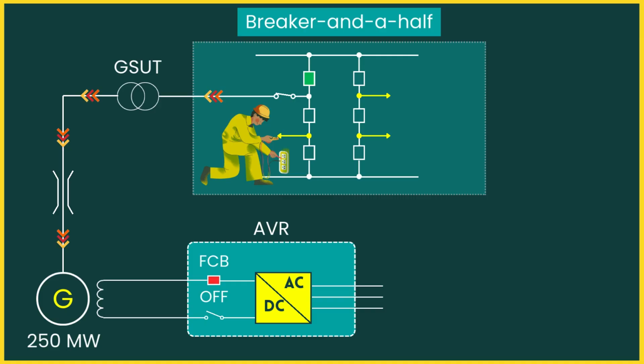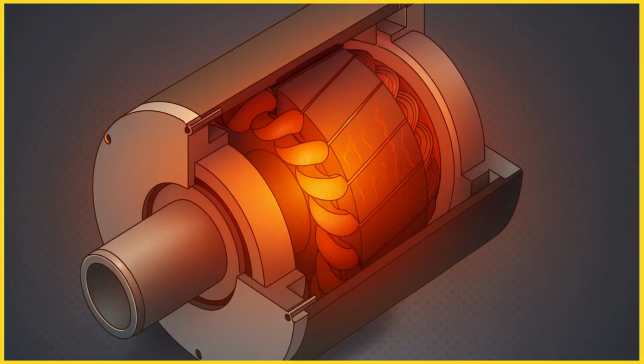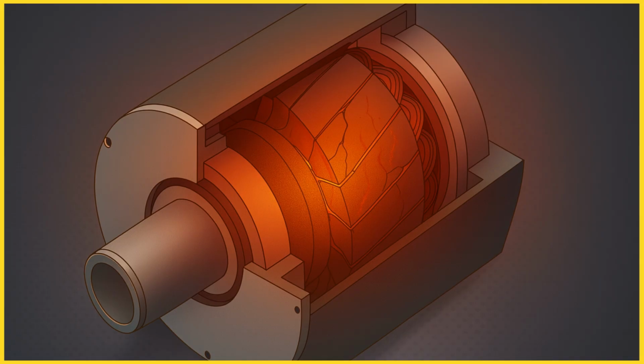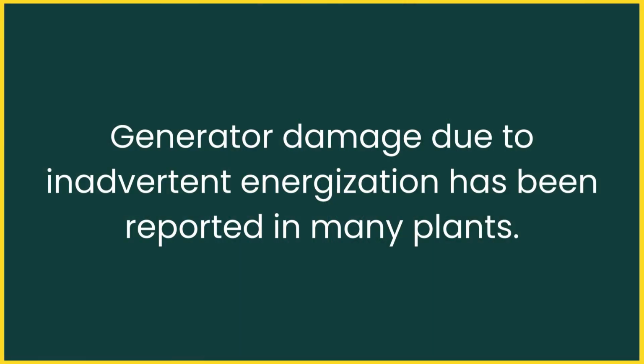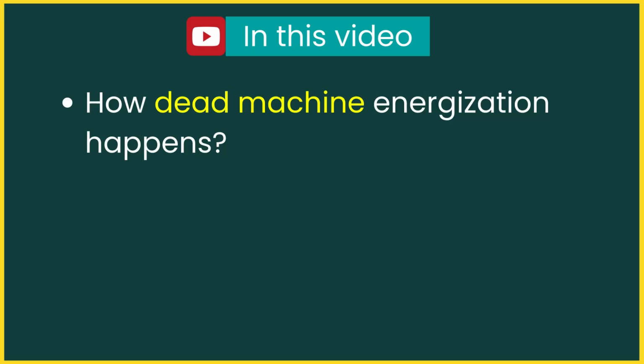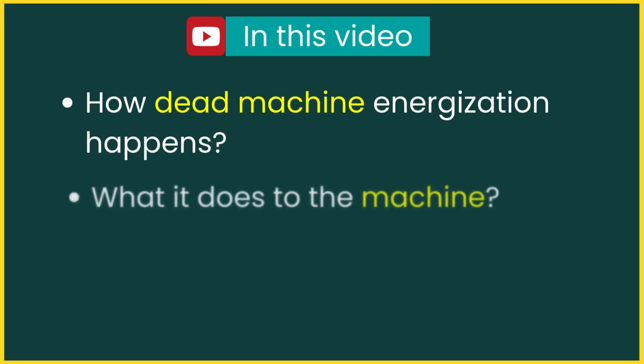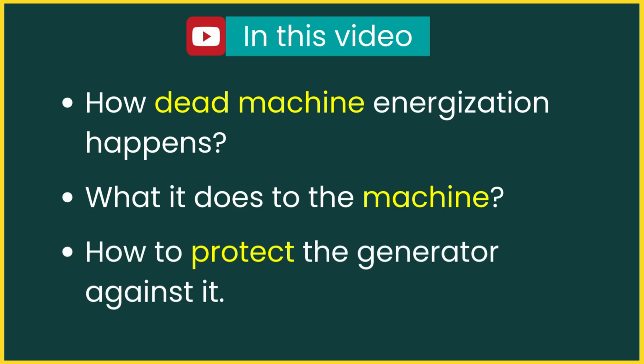Within just a few milliseconds, the rotor surface temperature began to rise sharply. By the time the plant operator noticed what had happened, deep thermal cracks had formed in the rotor body, and the unit remained out of service for months. And this is not an isolated case. Generator damage due to inadvertent energization has been reported in many plants. In this video, we will understand how dead machine energization happens, what it does to the machine, and how to protect the generator against it.